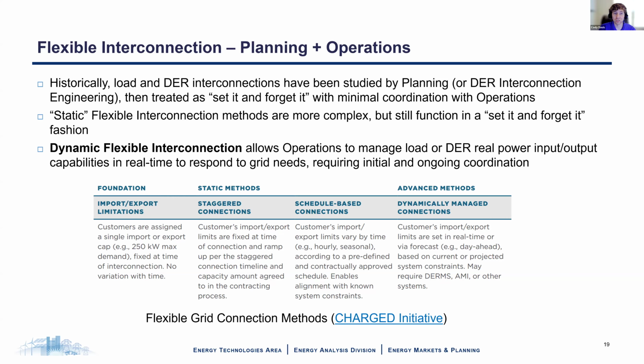That's changing. Flexible interconnection is driving some of this. There is a difference between static methods and dynamic methods. Static flexible interconnection is just changing the input assumptions that planning uses and how the resource behaves. So it's more complicated, but it's still basically a set it and forget it that operations doesn't care about. But dynamic flexible interconnection is the big curveball. This allows operators to physically set load or DER maximum real power input or output points in real time as grid needs change.